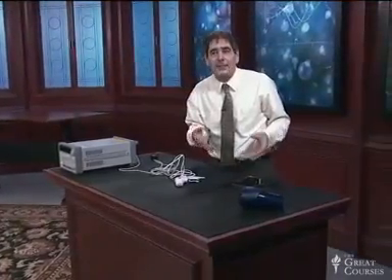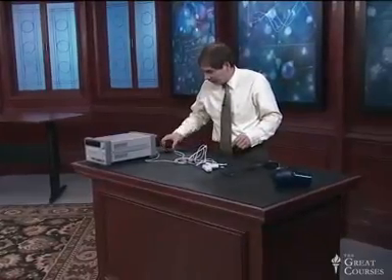And what the interrupter does is it senses the current flowing down one wire and the current flowing back the other wire. And if they aren't exactly equal, it assumes the current is leaking off somewhere, possibly through a person, and getting to ground some other way, and somebody's getting shocked, and so it shuts off the circuit before a dangerous current can develop. So those are some ways of protecting us from the dangers of electricity, the dangers of too much electric current flowing through us.